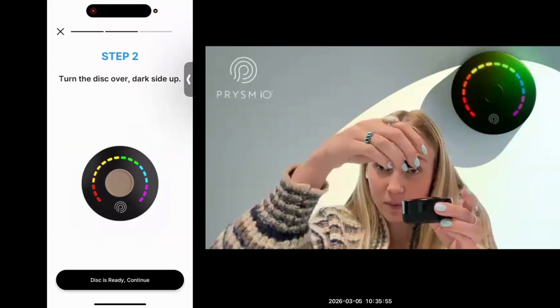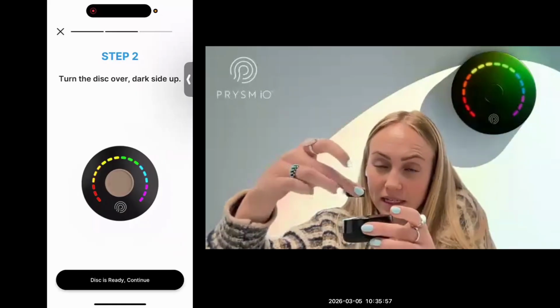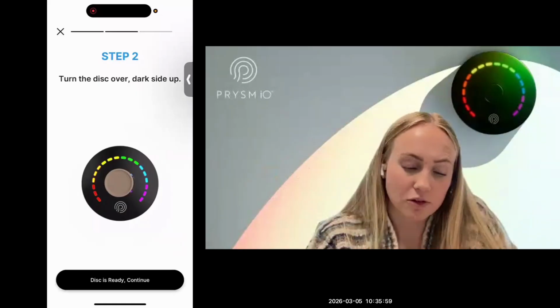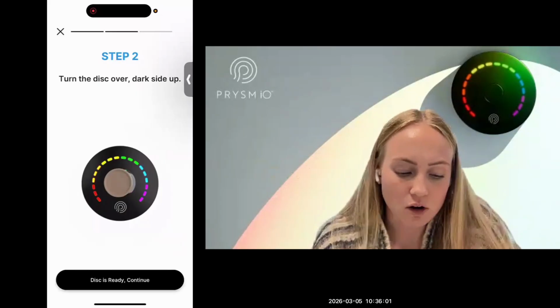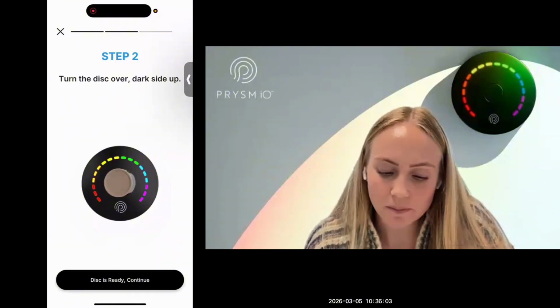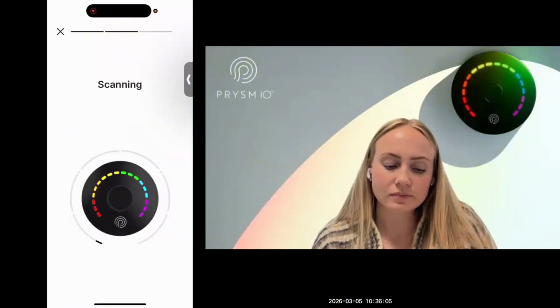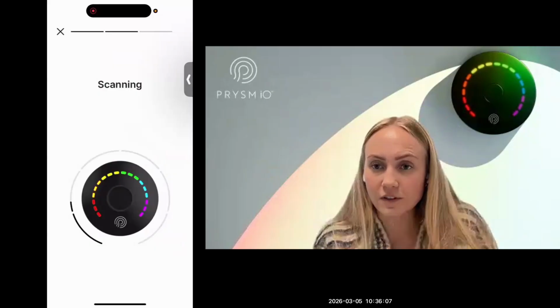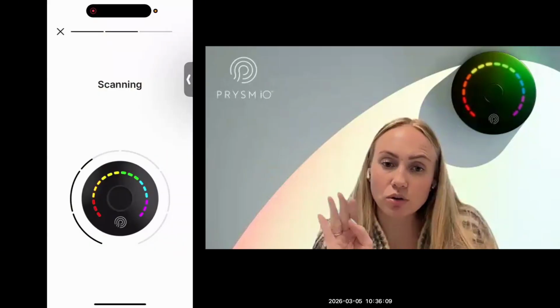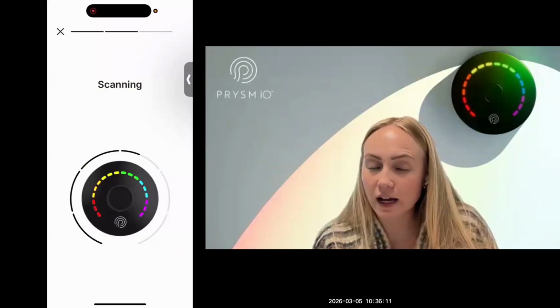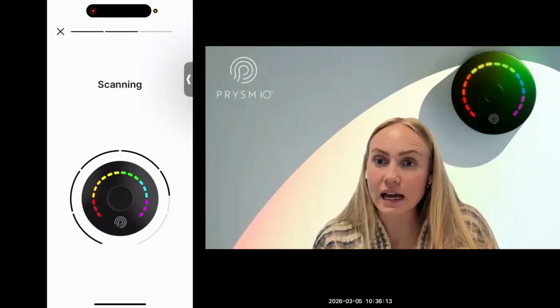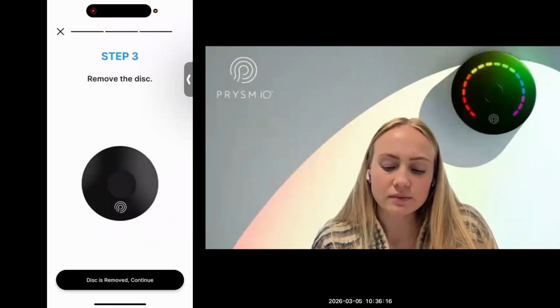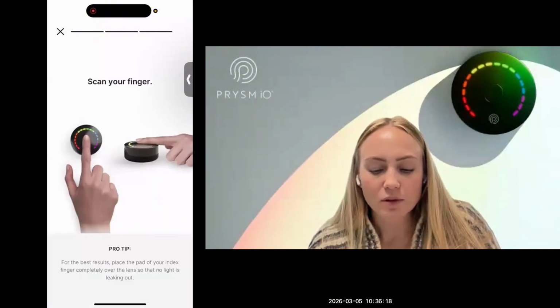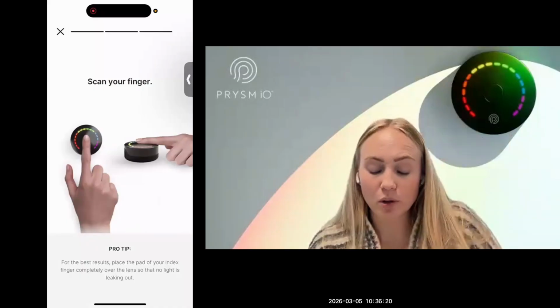Then it's saying to flip the disc. So I'm going to go from my tan side up to now my tan side being down. Place that over the lens. Once it's placed there, hit go ahead. This will do one more 15-second scan, and it's going to load those unique numbers onto the device to set that calibration. Then you hit that the disc is removed, so you go ahead and pull it off.